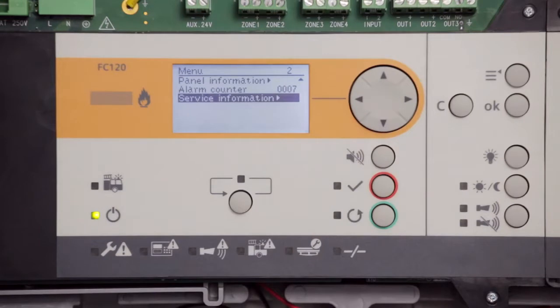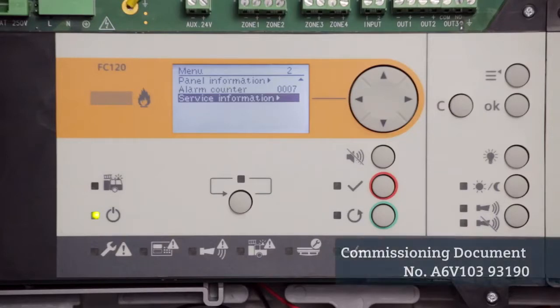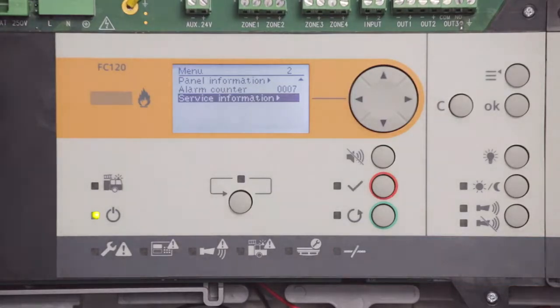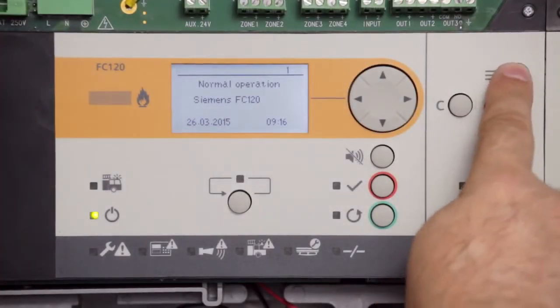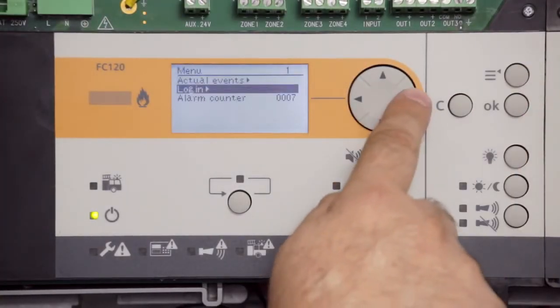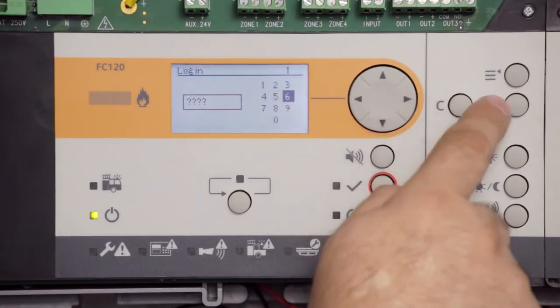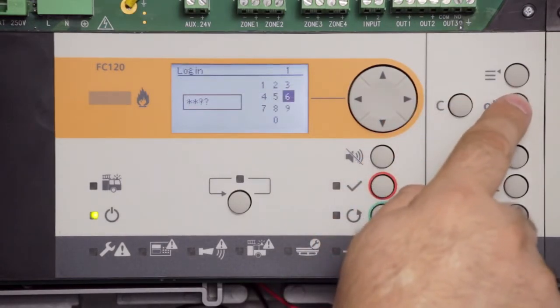In this video, we will focus only on the basic programming. For additional programming, please have a look at the detailed commissioning document number A6V103-93190. We will program customer text for zone and outputs only. Press the menu button on the right top side, enter the 4-digit code for level 3 access. Standard code for level 3 is 6666.